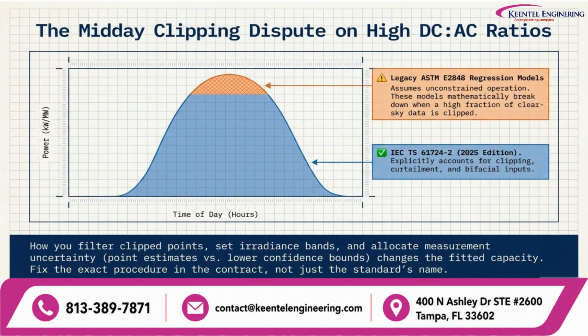Modern utility solar systems frequently feature high DC to AC ratios, resulting in pronounced midday inverter clipping. Legacy regression models, such as standard ASTM E2848, assume unconstrained operation and mathematically distort fitted capacity results when clipping truncates peak generation data. Contracts must explicitly adopt updated frameworks like IEC TS 61724-2 2025 edition, defining precise procedures for data filtering, irradiance thresholds, and measurement uncertainty bounds, rather than relying on ambiguous legacy standards.